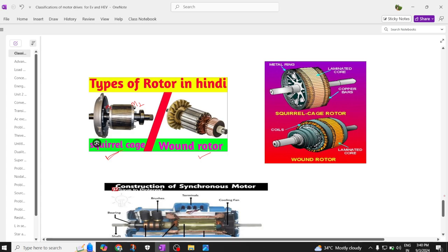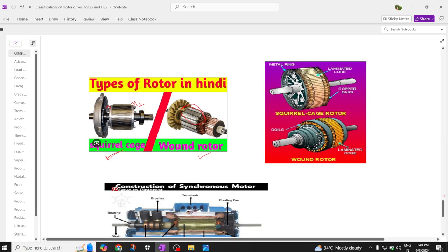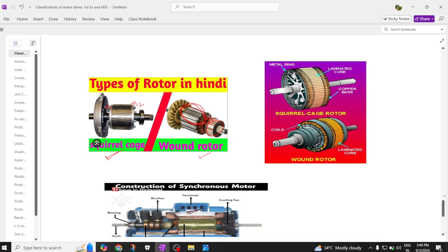The next type of rotor is the wound rotor. In this wound rotor, you have an iron core — this is nothing but a laminated core. In this laminated core we are going to have the windings in the slots. You can see the coils starting and ending — the coils are wound like this and they are brought out. These windings are connected to the slip ring. They are brought out and connected to the slip rings, and these slip rings have contact with the copper brushes.